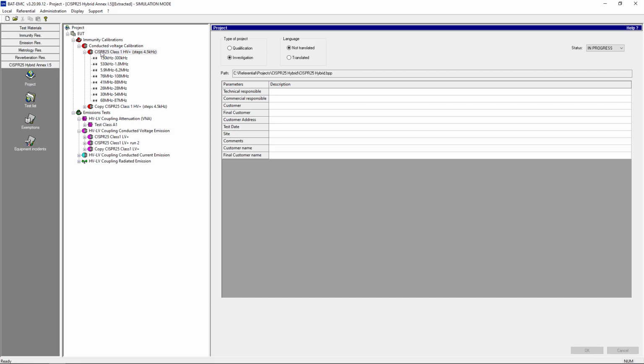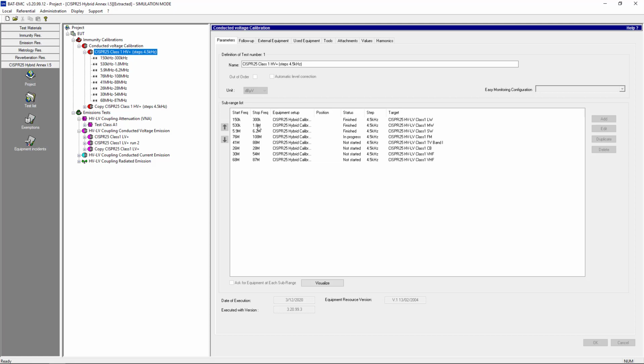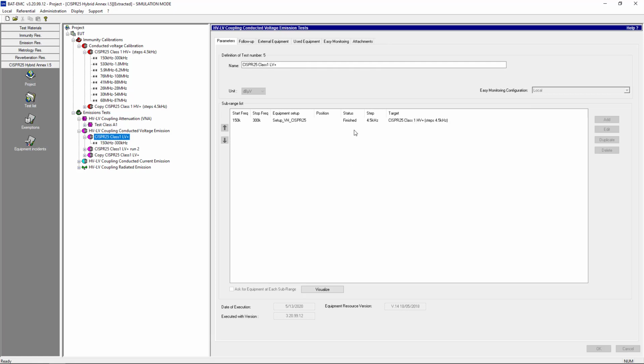This was just a partial calibration to get things rolling. To do so, it would have to have been done on these individual frequency ranges as well as the plus and minus side. This was just the plus. And if we look at one of these tests, let's look at this test for example. You can see there's only one subrange listed here. It would have had to have been done for both the plus and minus side of low voltage.